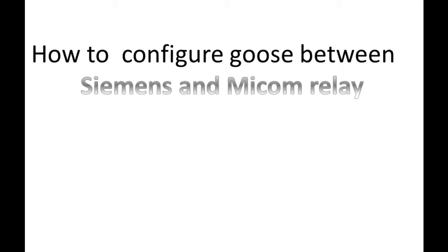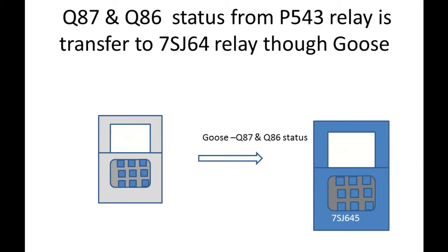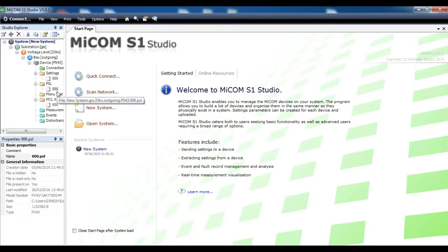Here we are going to see how to do GOOSE between Micom and Siemens relay. This is the SLD from this. The line isolator and earth isolator is taken to Micom P543. And we are using another BCU relay which is a Siemens. For that BCU relay, the isolator status is required. For that I am going to take a signal from Micom to Siemens through GOOSE for these two isolator statuses.